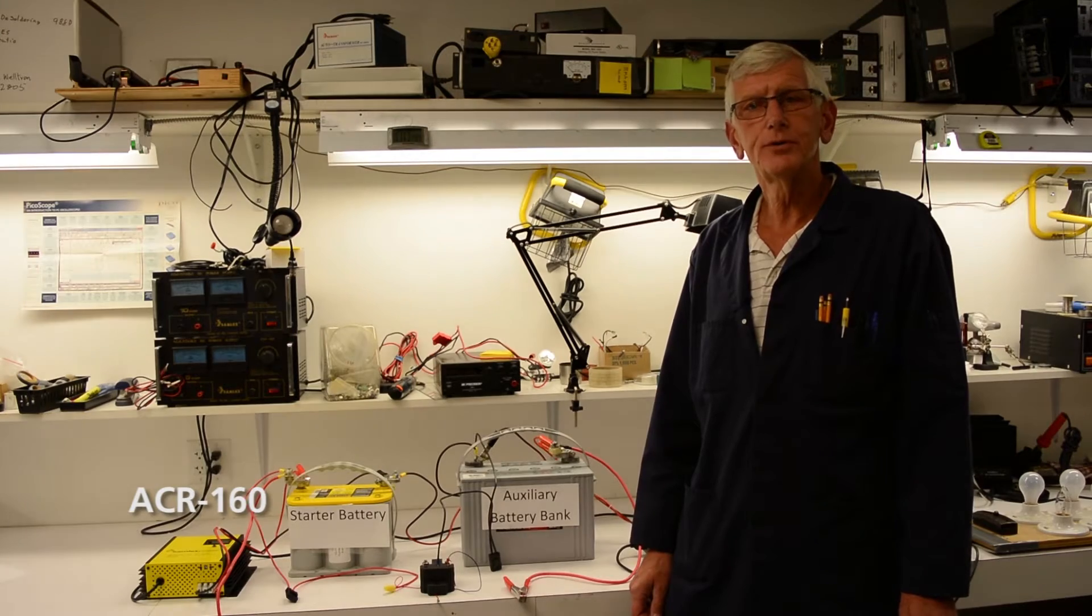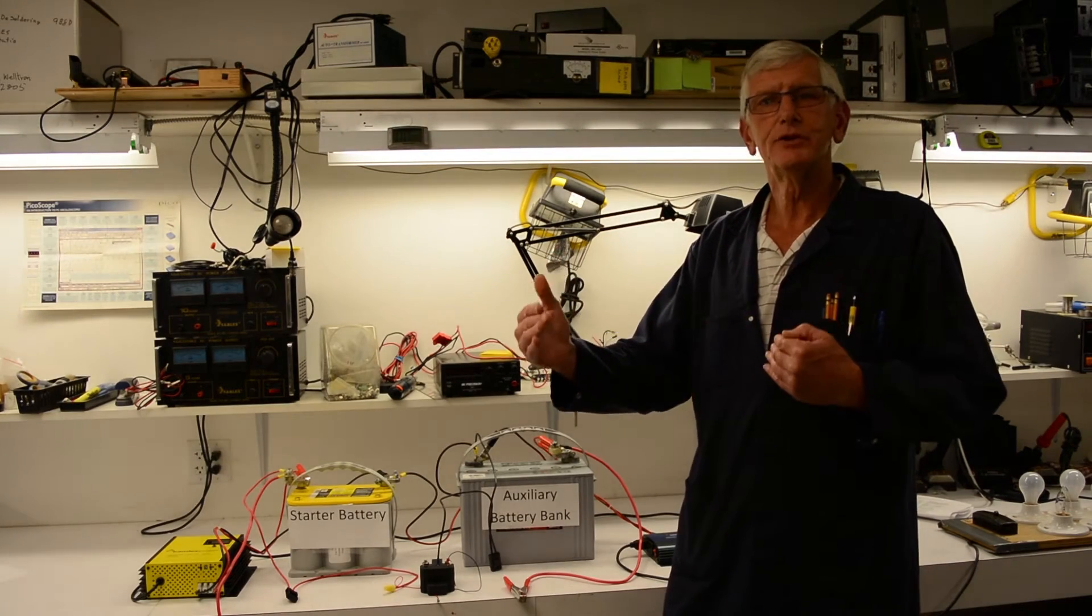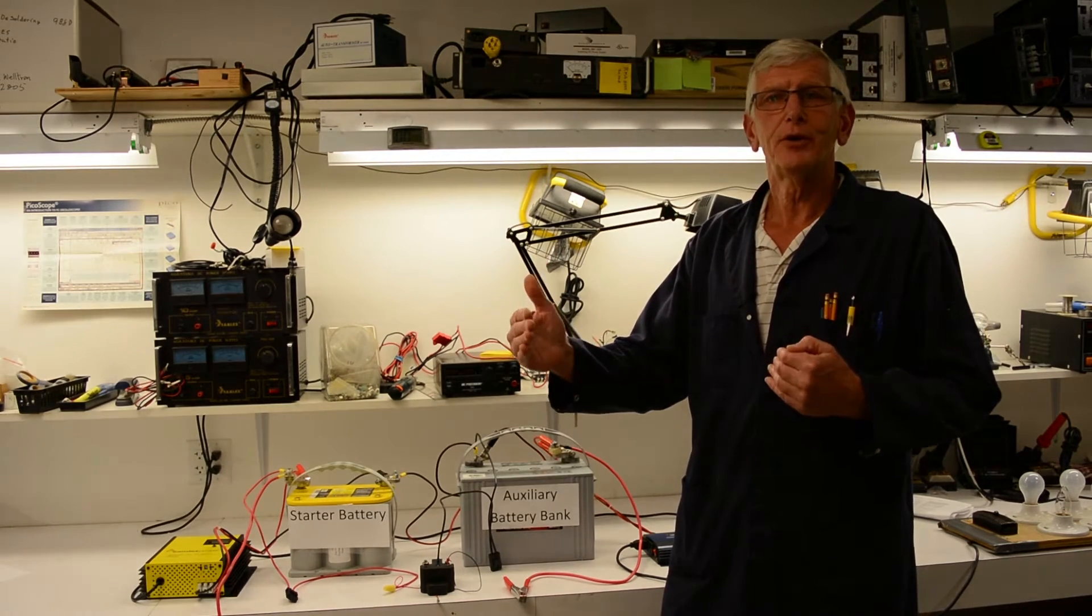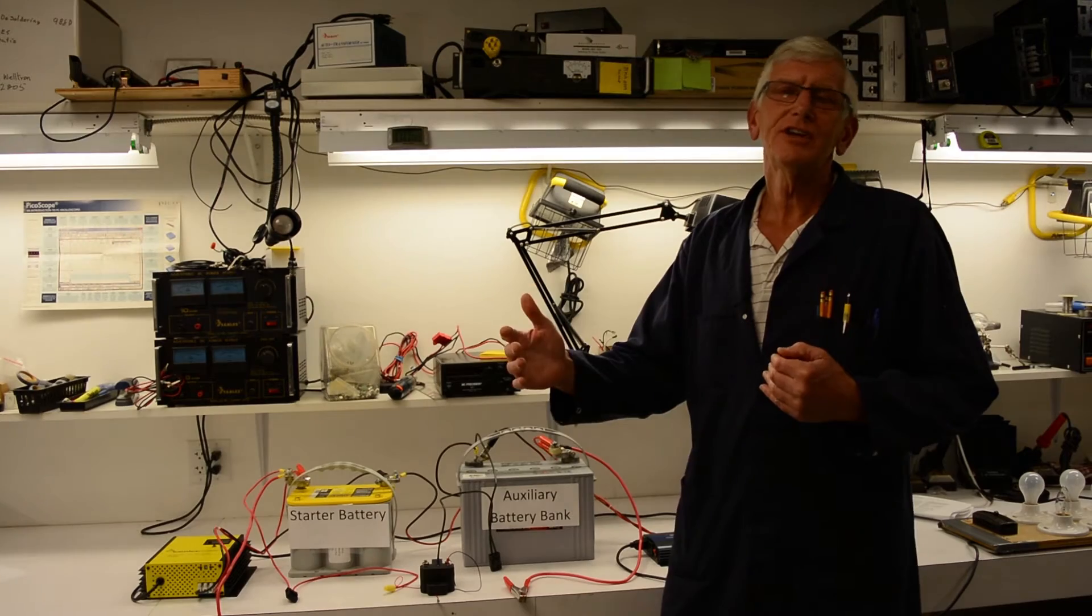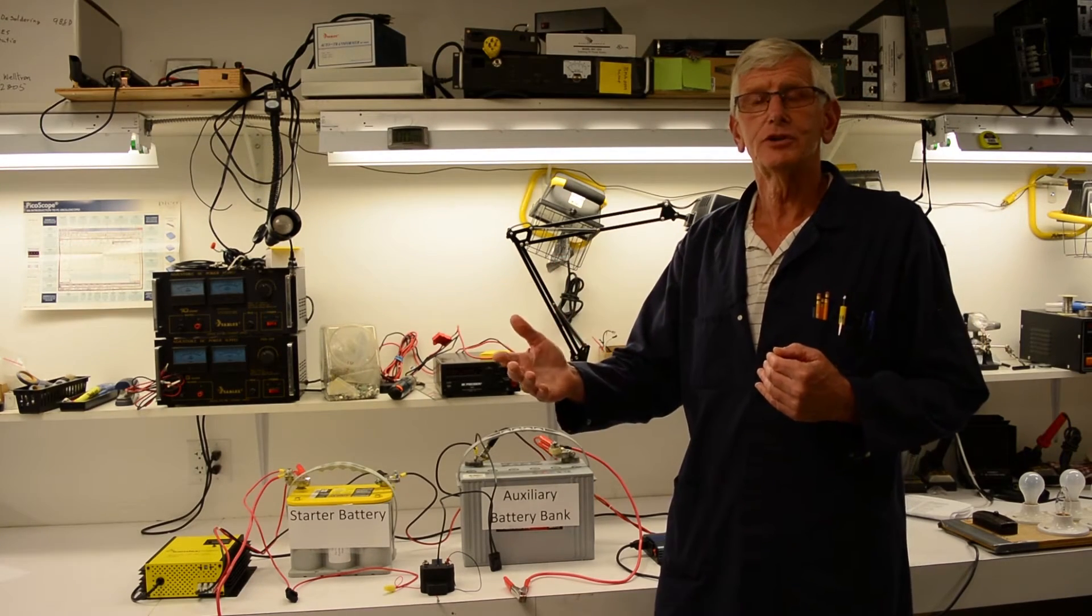The ACR-160 is a voltage dependent relay that will make or break a connection between two battery banks based on the voltage that those battery banks have. And what it does, it saves you from deep discharging one of the banks.